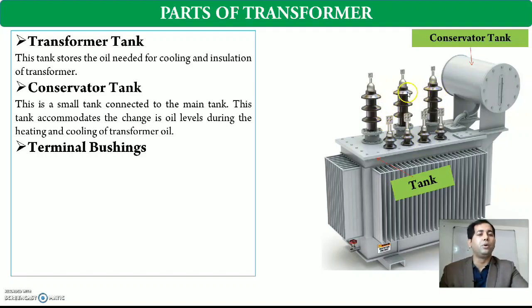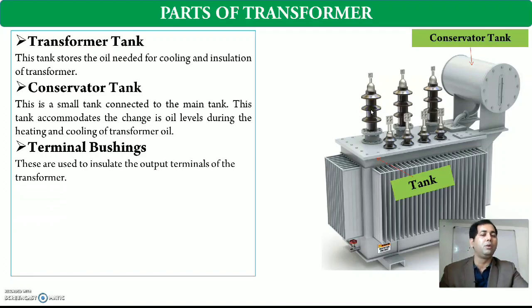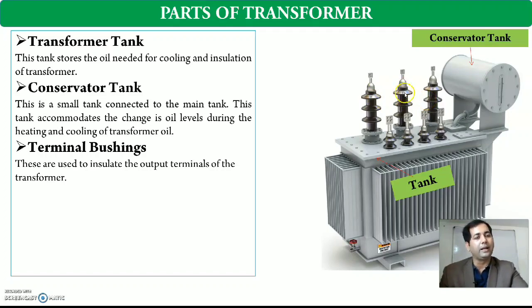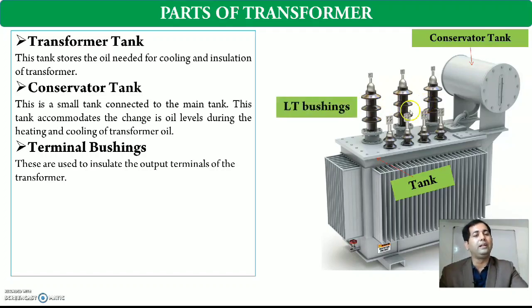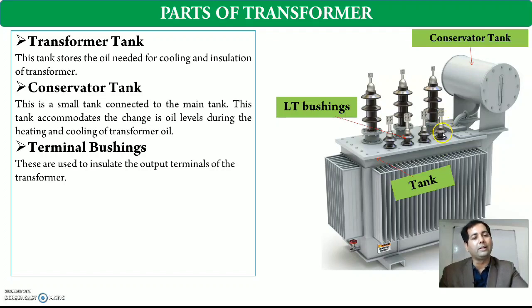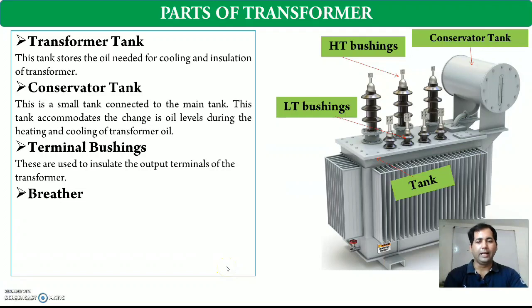The third point is terminal bushings, which are just like insulators in transmission and distribution networks, but with different ratings. There are two types of terminal bushings: HT (high tension) bushings and LT (low tension) bushings. The purpose of terminal bushings is to insulate the input as well as output terminals of the transformer — insulating the transformer body from the windings. For the high voltage side we use HT bushings; for the low voltage side we use LT bushings. In a three-phase transformer we have three LT bushings, one earthing/neutral point bushing, and three HT bushings.